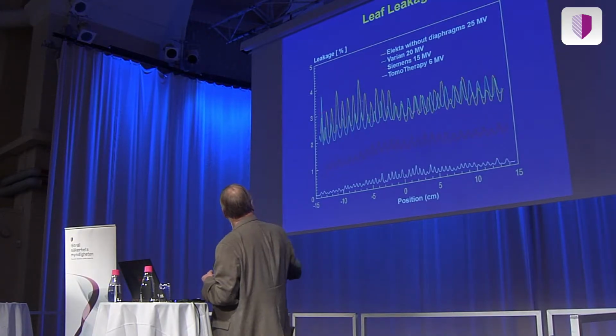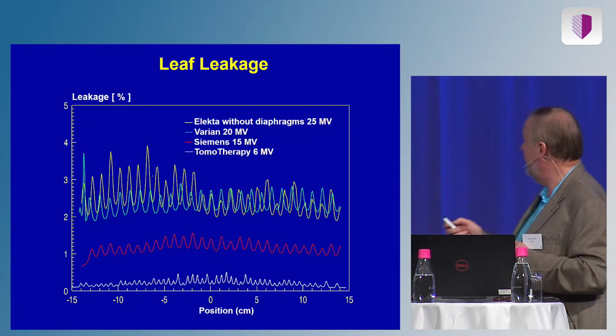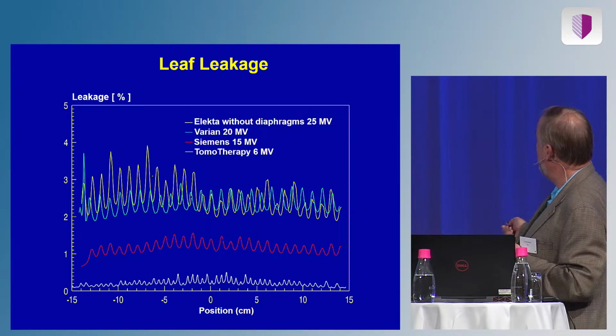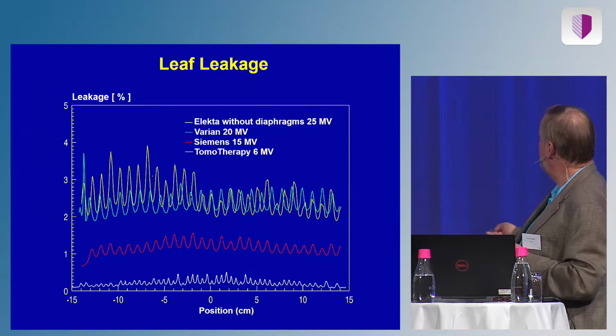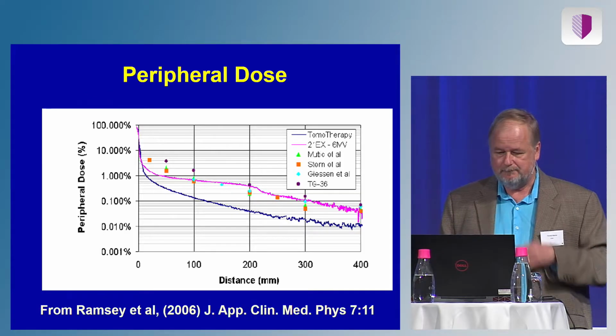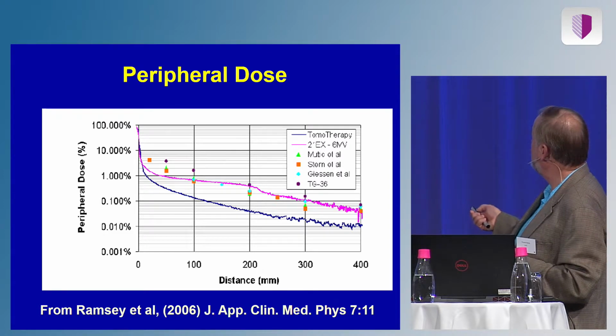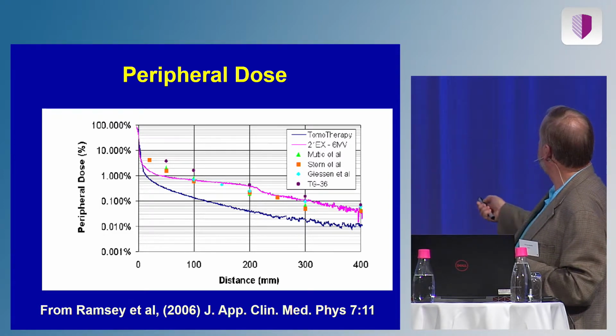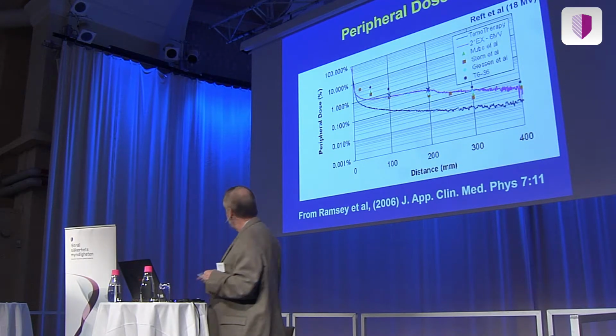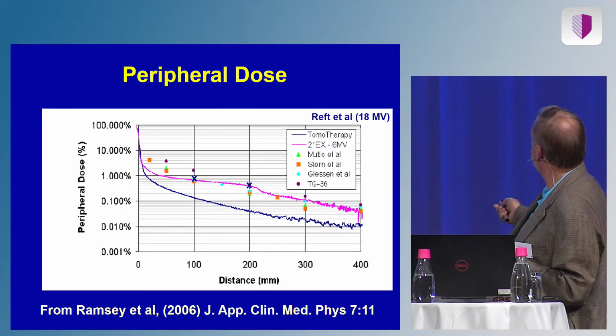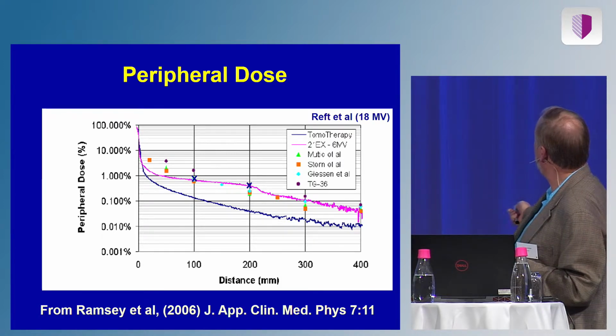You also have to look at the leaf leakage here, and here are some conventional C-arm gantries. Again, they were originally the collimators, and these systems were built to do 3D conformal. They weren't built for IMRT. Siemens built a system that had thicker leaves by another centimeter of tungsten, and then tomotherapy added 2 more centimeters of tungsten. And so you can see it's possible to reduce the leaf leakage a lot, and this can be important. And then the peripheral dose, this is the dose that's entirely due to leakage. I think we have the energy listed here. Yeah, it's 18 MV here, as compared to a 6 MV beam, which I plotted on top of here, as well as tomotherapy.